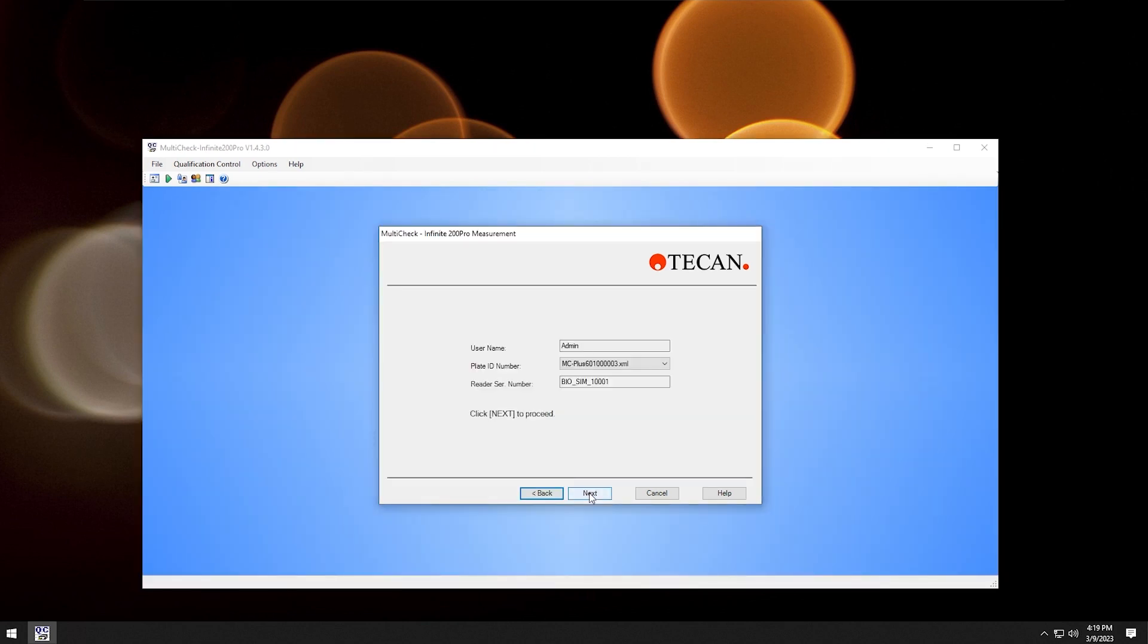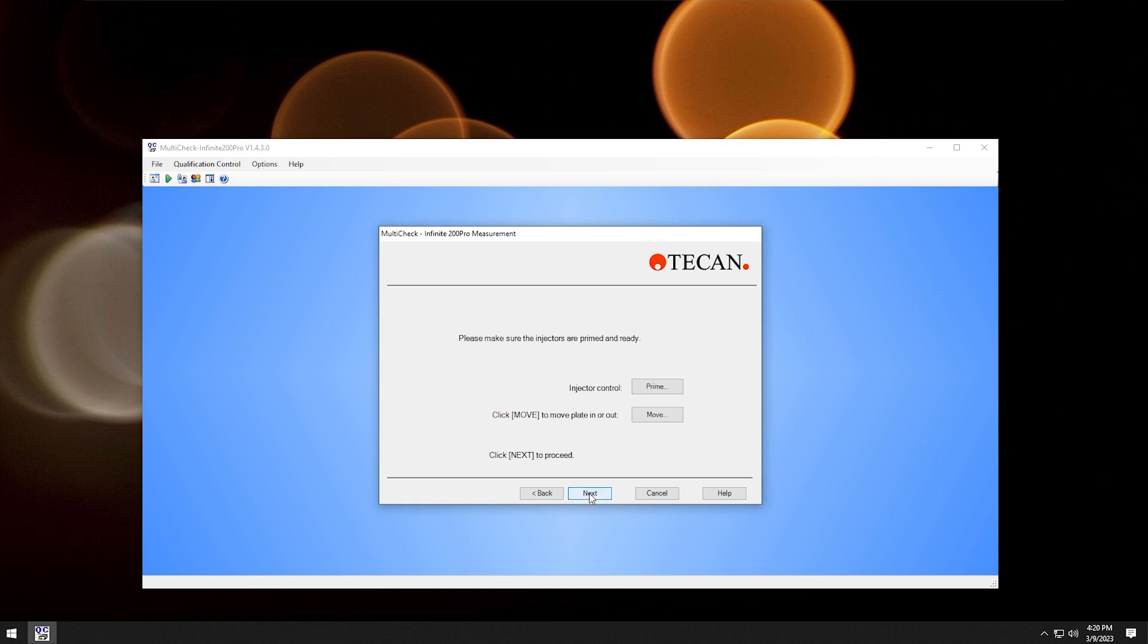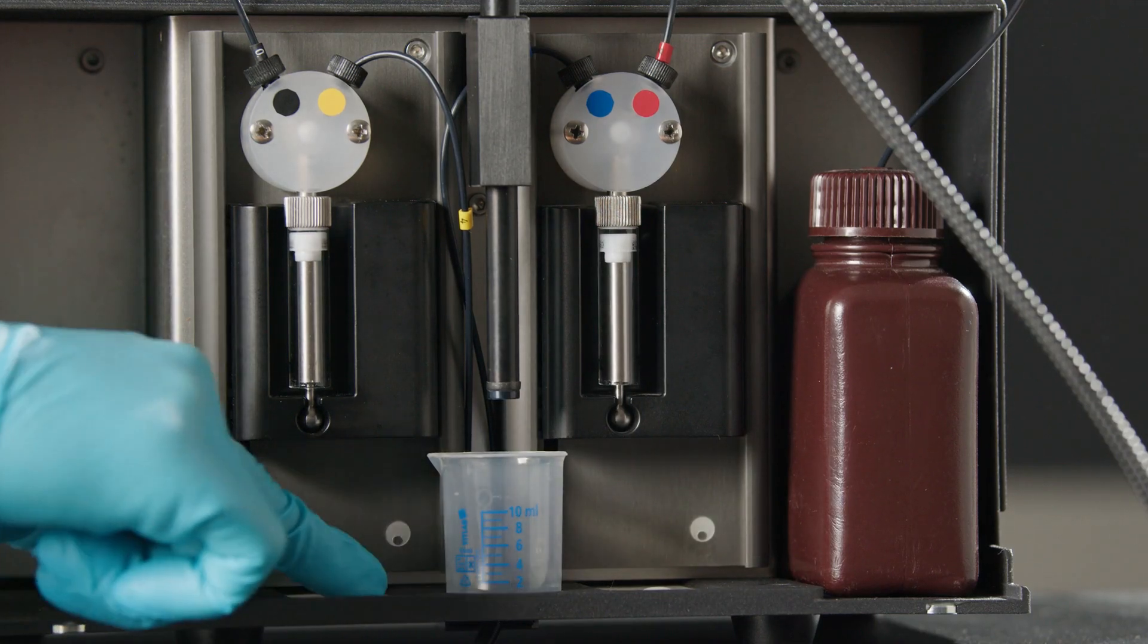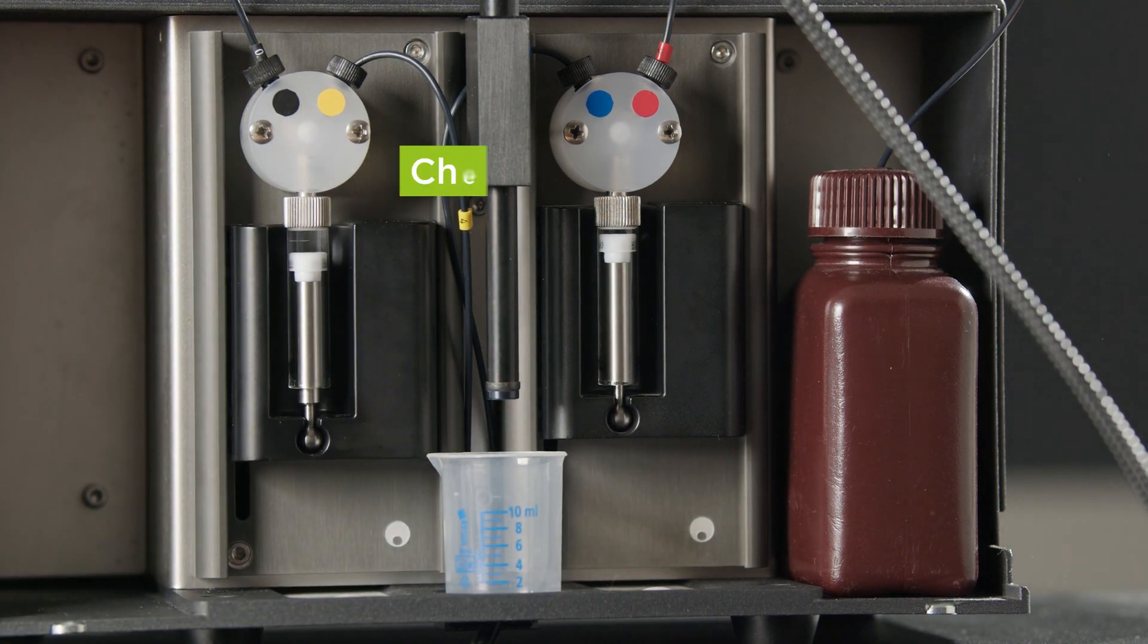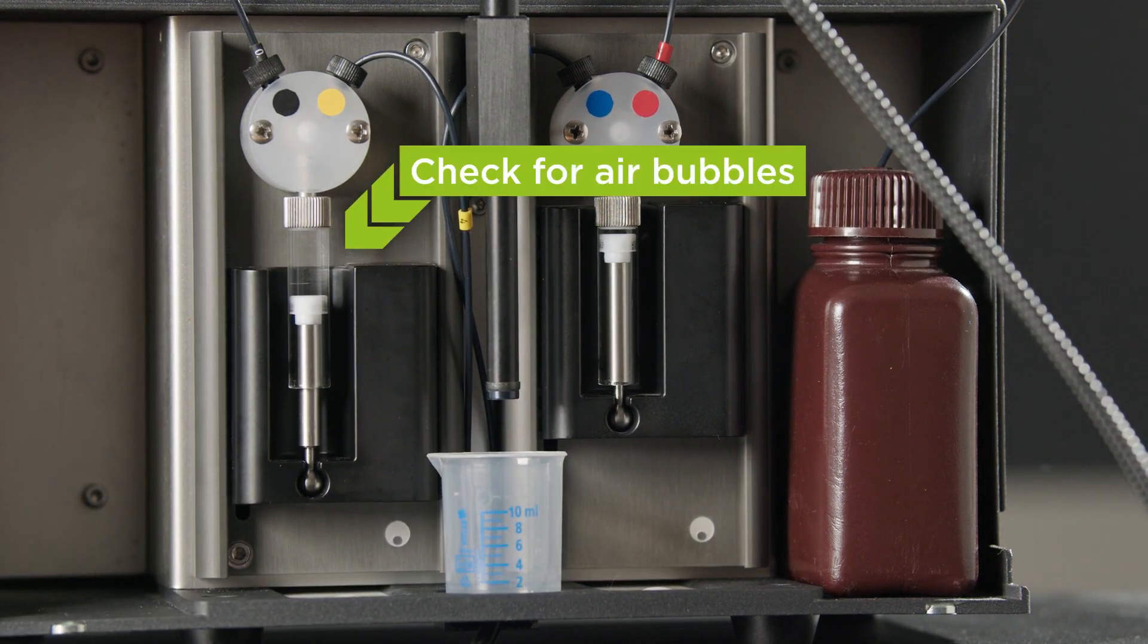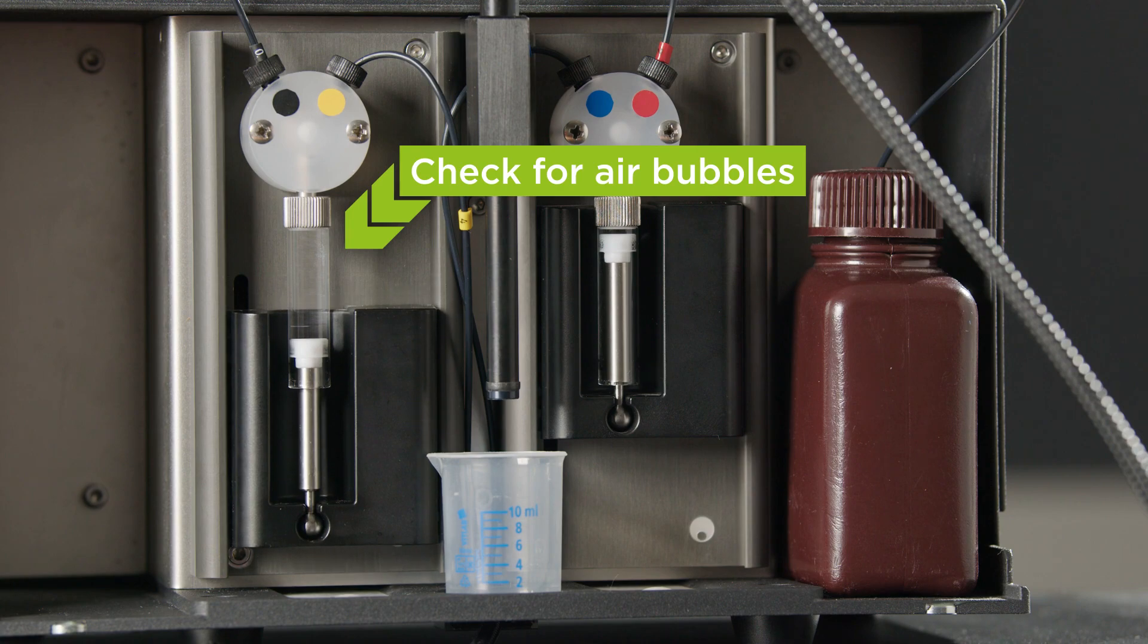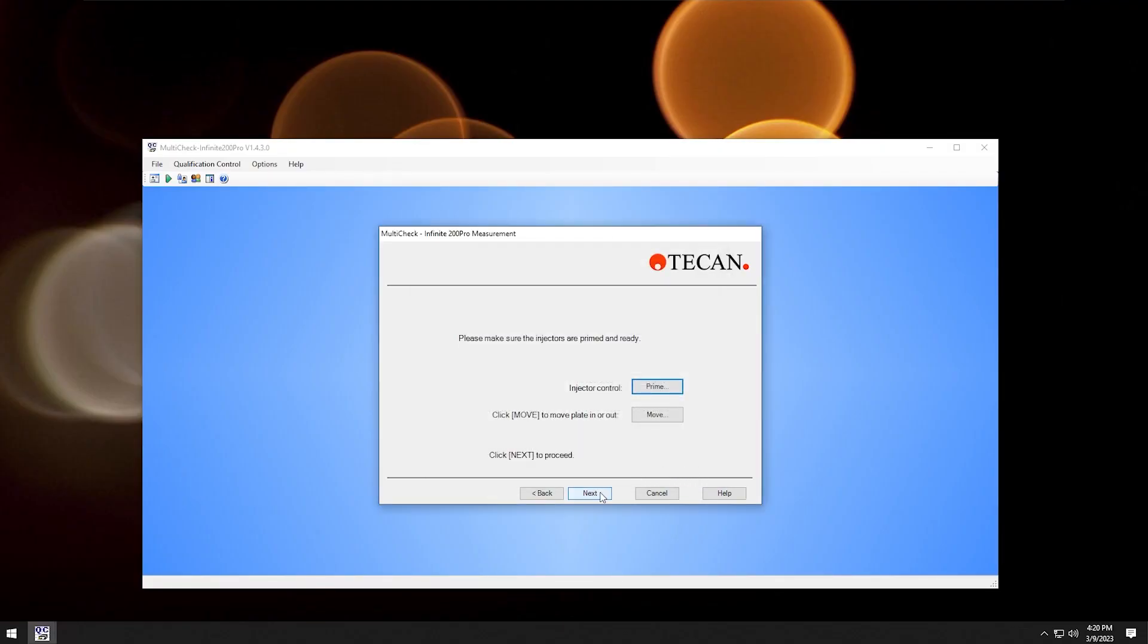Click next again. The provided tests should all be automatically selected, so click next. If the injector is installed, we have to prime the instrument first. Choose your injectors and start the priming process. After priming, close the window and click next.